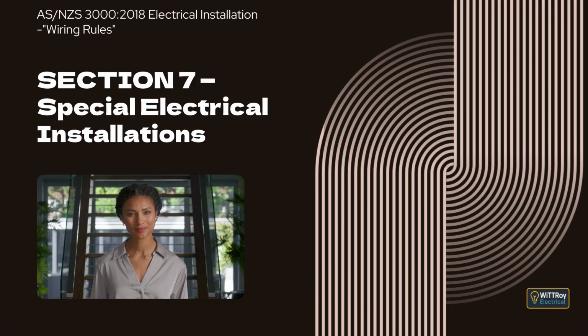Clause 7.2.10.4 Wiring systems. This clause introduces wiring system requirements for MRL lifts. Clause 7.2.10.4.1 Types of wiring systems for MRL lifts. This clause explains that wiring systems supplying MRL lifts must comply with AS/NZS 3013 and use the wiring system classification specified by the relevant installation standard.